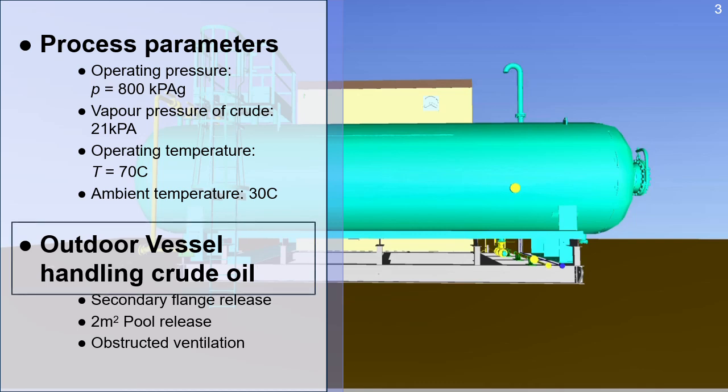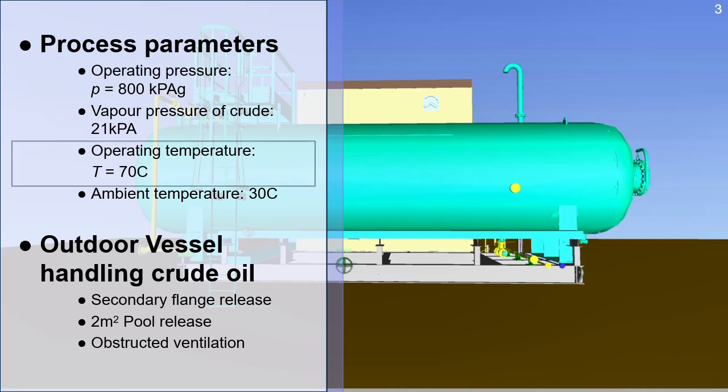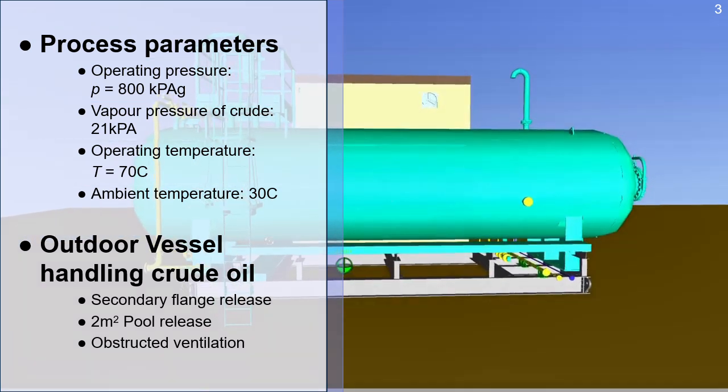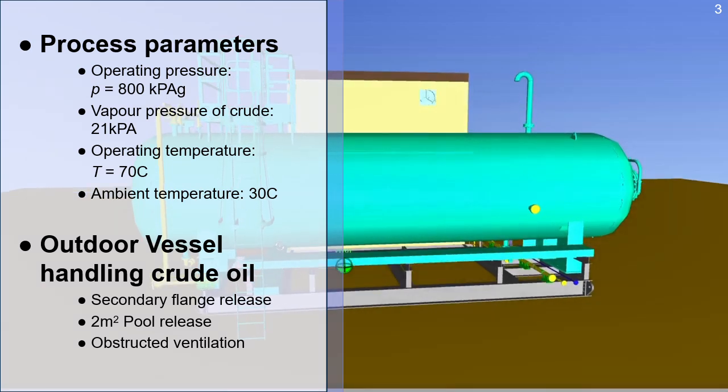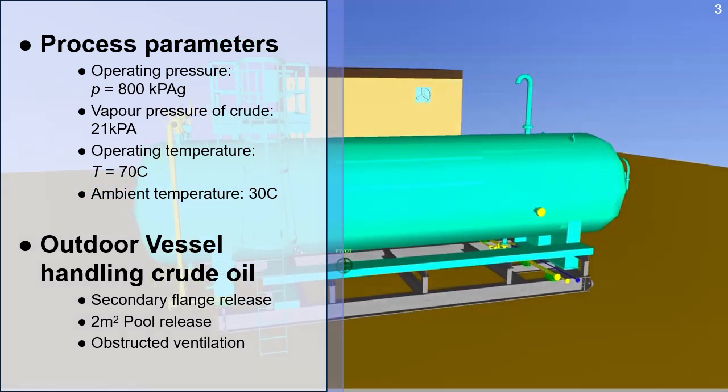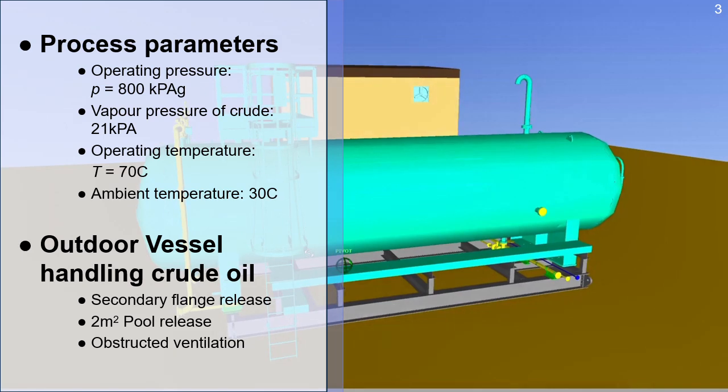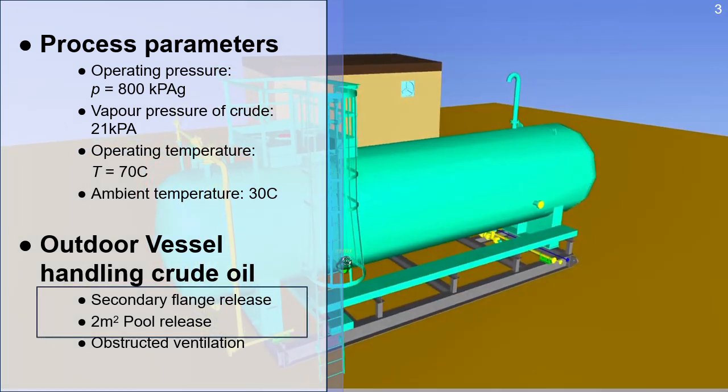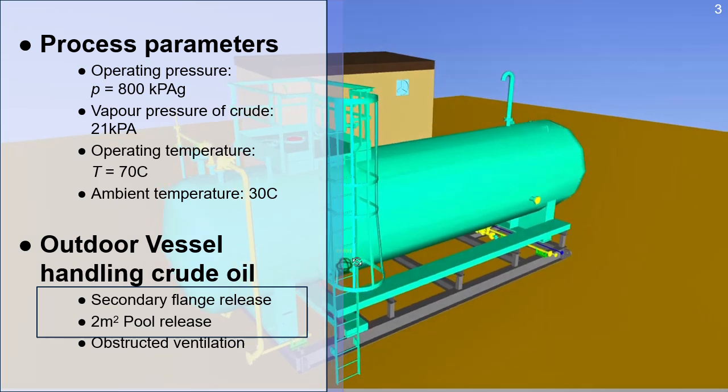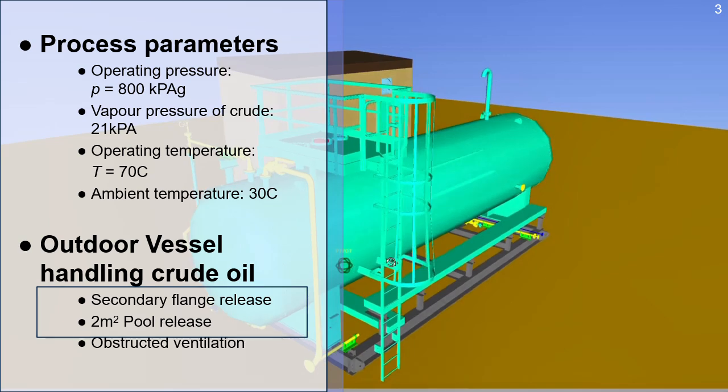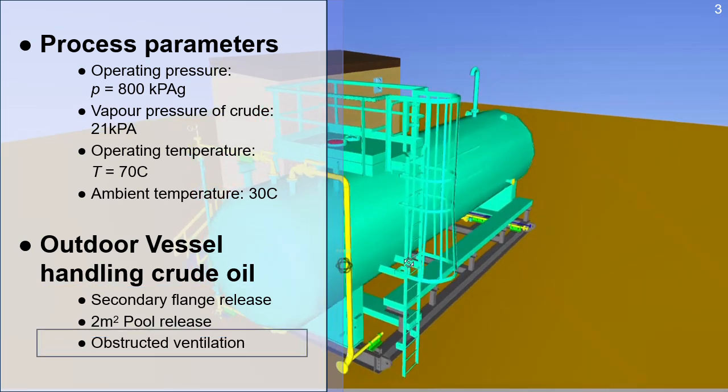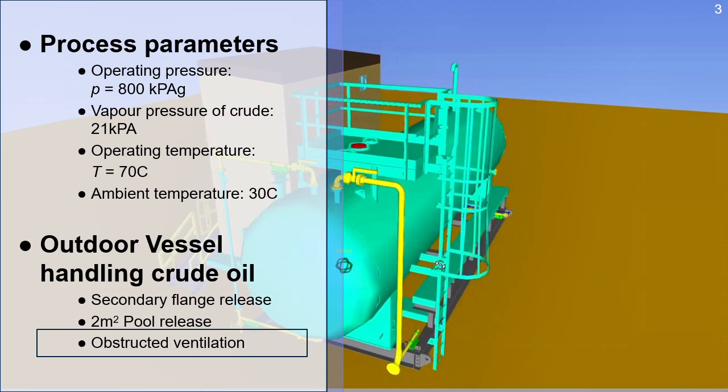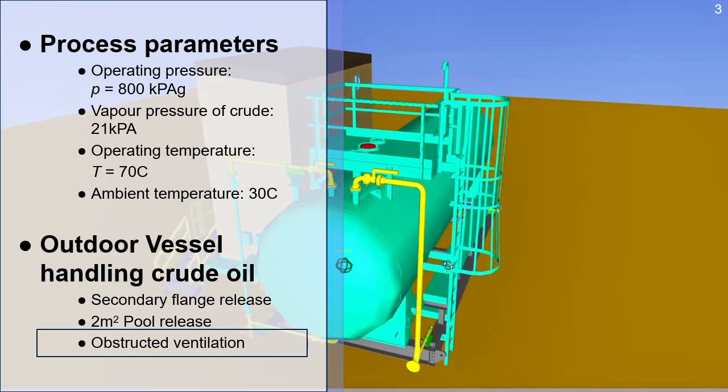The vessel handles light crude oil operating at 800 kPa and 70 degrees Celsius. The vessel is incorporated into a manned facility that incorporates twice-daily routine checks by operations. A crude release would be quickly identified, and it is estimated that the size of pool released would be less than 2 square meters. The area is obstructed by the building, and this may compromise the level of ventilation in the area.